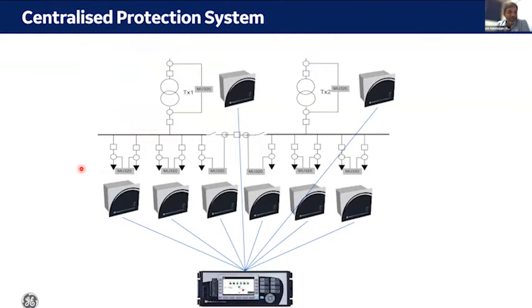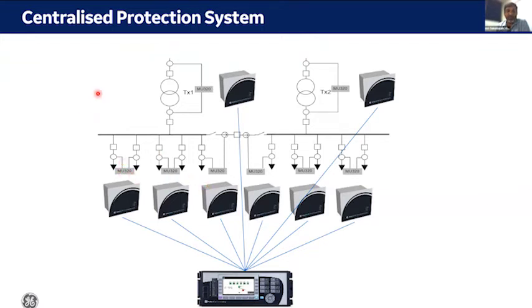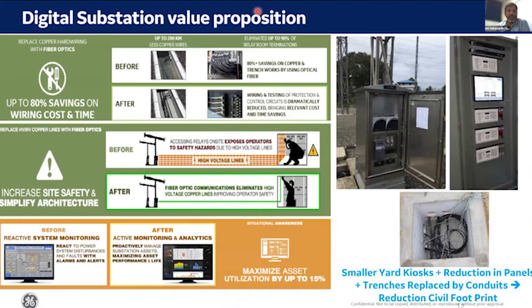In a digital substation, merging units provide sample values for each bay available on the network. In sub-transmission networks, instead of a separate backup relay per feeder, a centralized protection concept can provide backup protection to all feeders. This kind of optimization through the process bus is one of the benefits available to users when adopting digital substations.